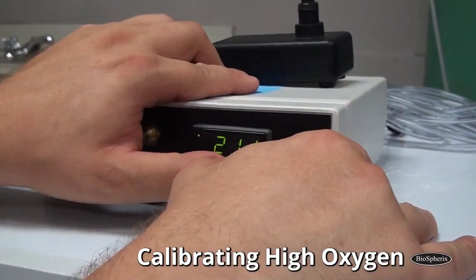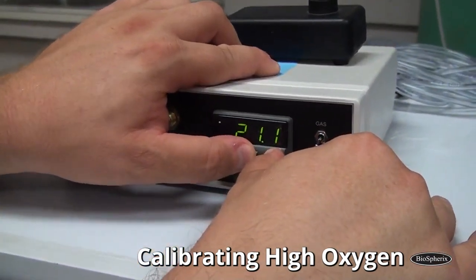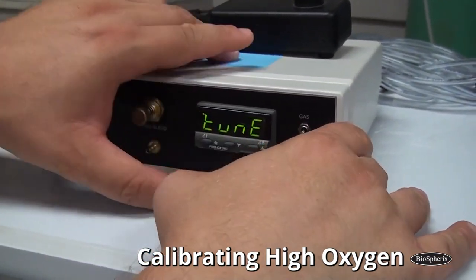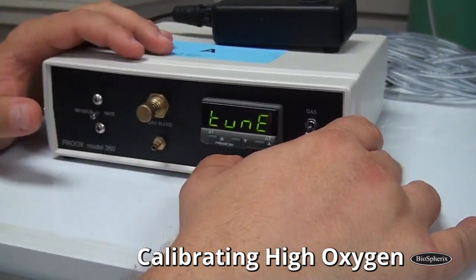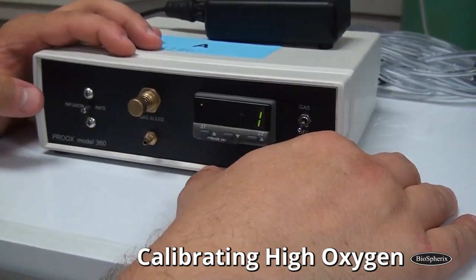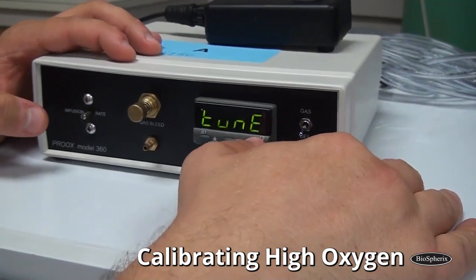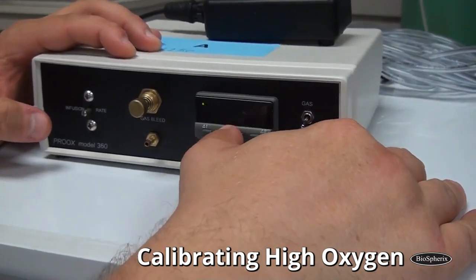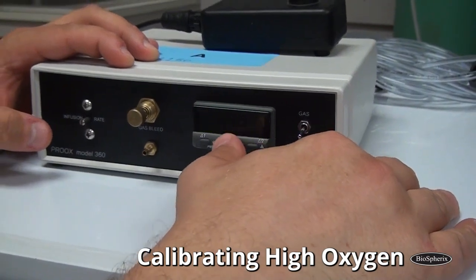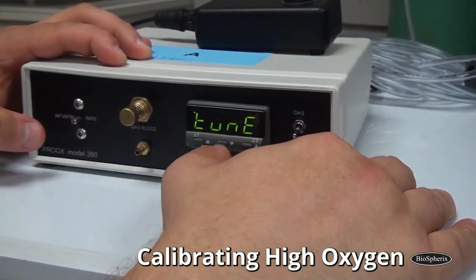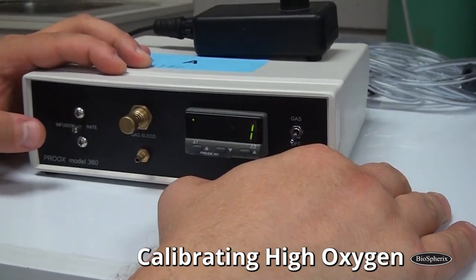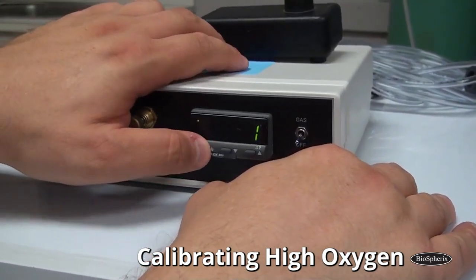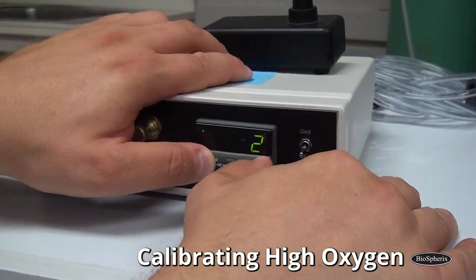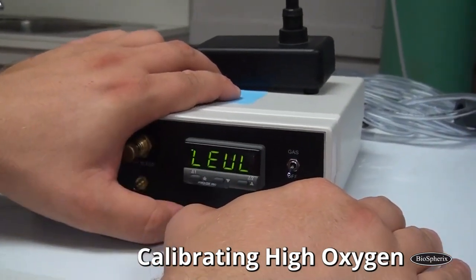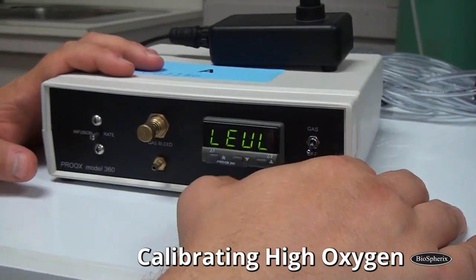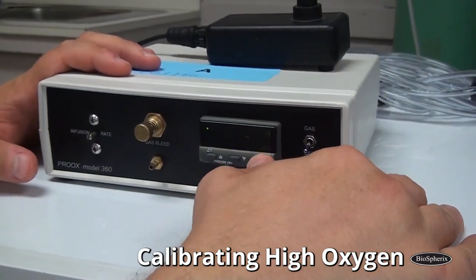So I need to go into the program mode. I hold up and down for 3 seconds to do that. Once I see the word tune, I can let go. And I'll press down once to get to the level function. And if you get lost, I just want everybody to feel comfortable going through the levels. You just press up or down and you go through all the different functions. So just press down until you see level. And we need to be on level 3. So I hold the star because I want to make a change. Press up twice. I'm on level 3. And then I want to scan through level 3 until I see 0.